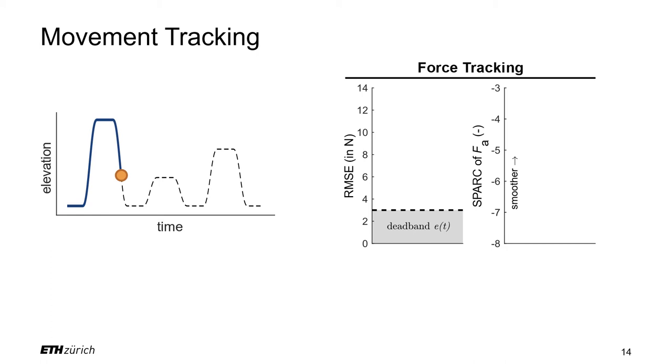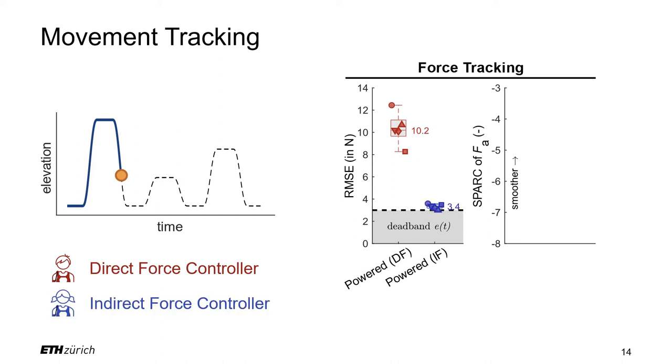However, in line with bandwidth results, force tracking errors were larger for the direct force controller, while interaction forces were close to the controller deadband of three newtons for the indirect force controller. Similarly, force tracking was smoother when the indirect force controller was engaged.